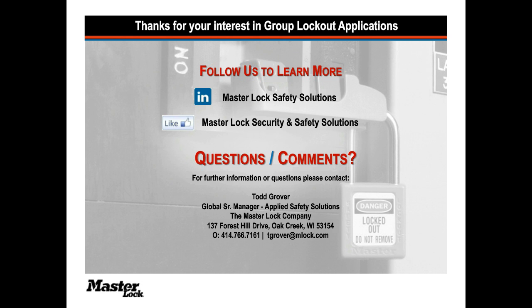In larger circumstances, let's say that we have 40 workers involved in a project, it would be very hard to walk all 40 through. And so that's where my description of a lockout leader following the procedure, placing the first lock, comes in. Independently, a verifier comes through, following the procedure and seeing if they agree or not with the placement of the first lock by the first leader, and then verifying by the addition of a second lock.